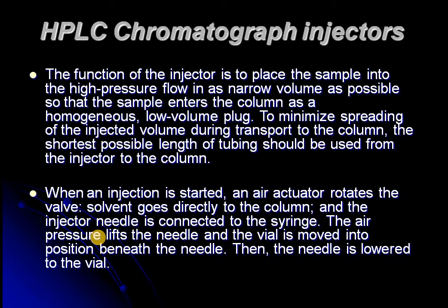HPLC chromatograph injector. The function of the injector is to place the sample into the high pressure flow in as narrow a volume as possible, so that the sample enters the column as a homogeneous low volume plug. To minimize spreading of the injected volume during transport to the column, the shortest possible length of tubing should be used from the injector to the column.